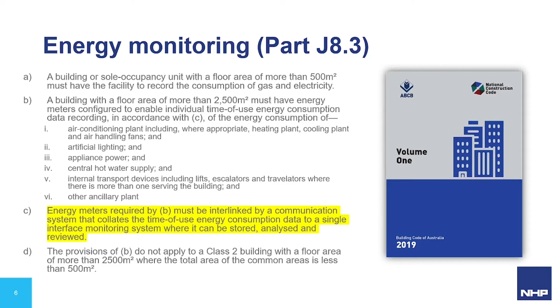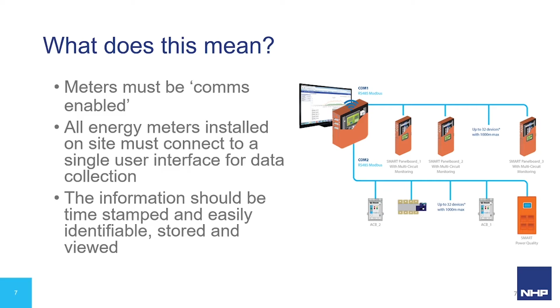So what does this mean for new installations? Well, energy meters must be comms enabled. Common protocols include Modbus and BACnet. All meters installed on site must connect to a single user interface for data collection. That energy data must be time and date stamped, and the information should be easily identifiable, i.e. labelled according to the circuit that it's monitoring, such as lighting or HVAC or power. The EMS interface must also be able to store the data for a reasonable period, although minimum storage time is not specified.